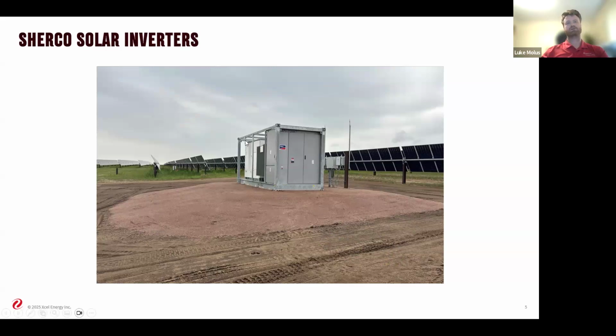The actual inverter portion of our inverter that takes DC to AC is this white box back here on the skid. It comes into the IGBTs, or power stacks, gets converted to AC at 630 volts, goes to our step-up transformer, which converts it to 34.5 kV, and then it goes into our switchgear here at the gray box at the end of the inverter. And then out of the inverter, the MV goes underground about 4 feet deep, and it runs back to our substation.